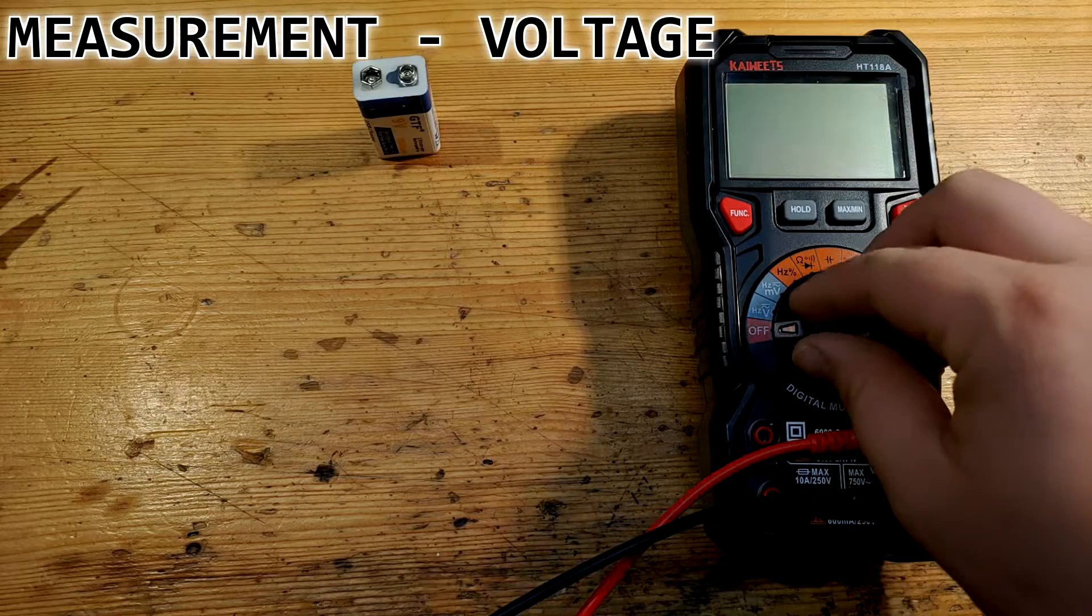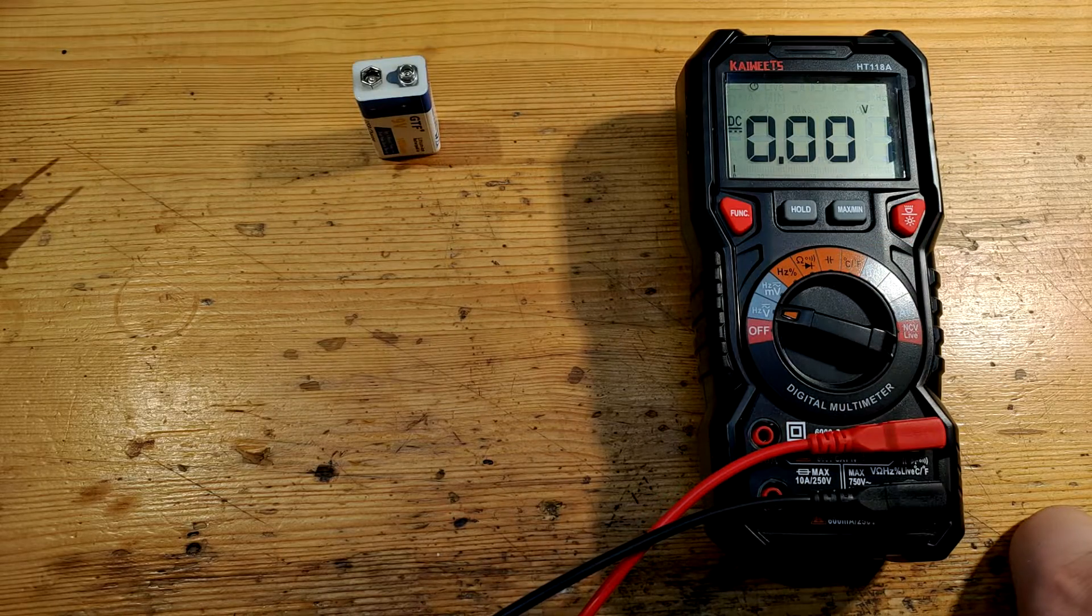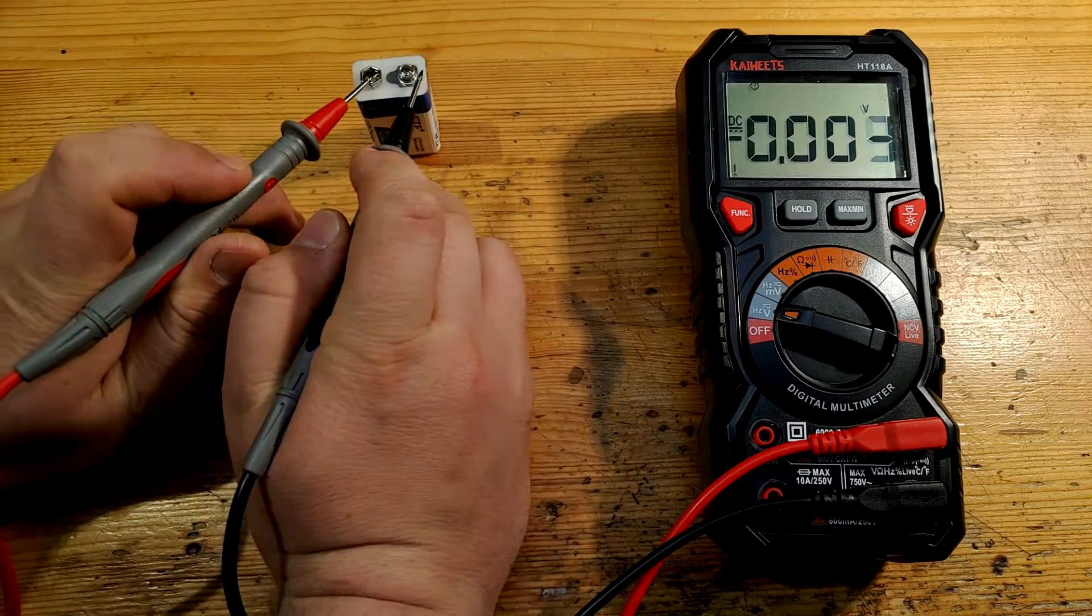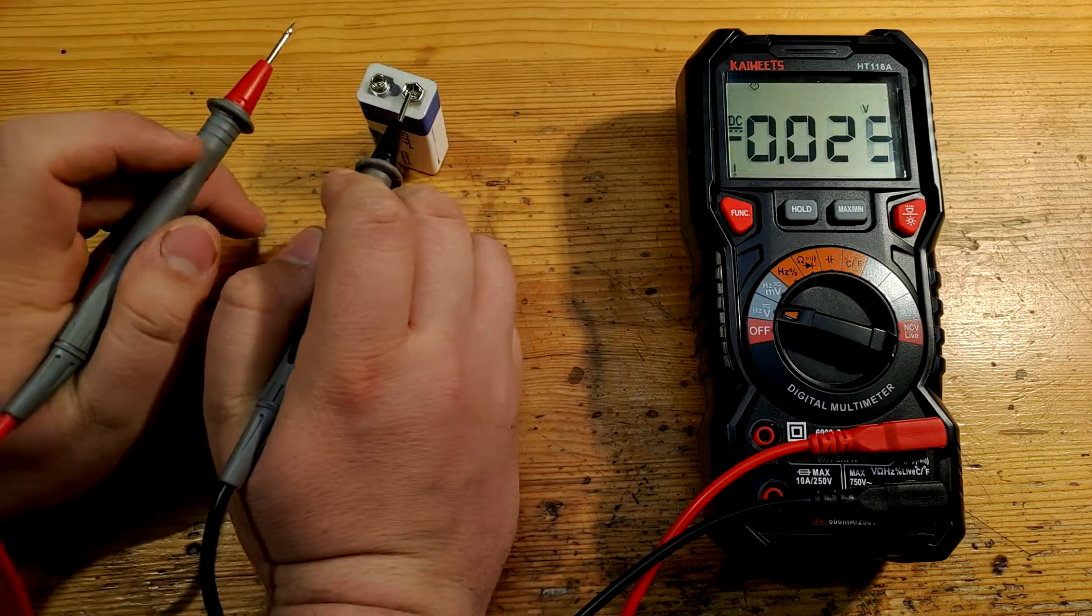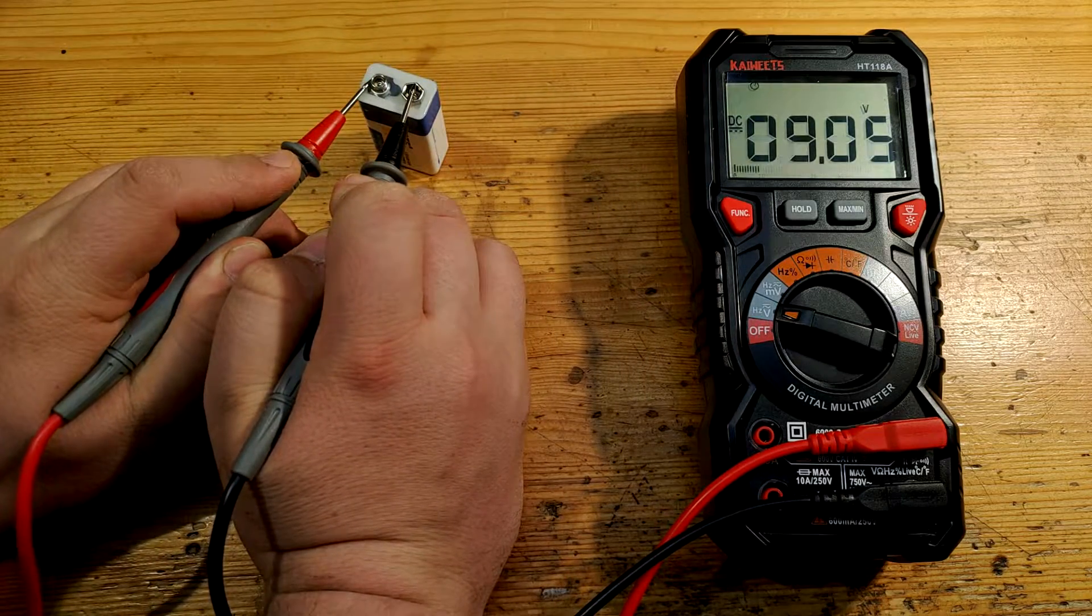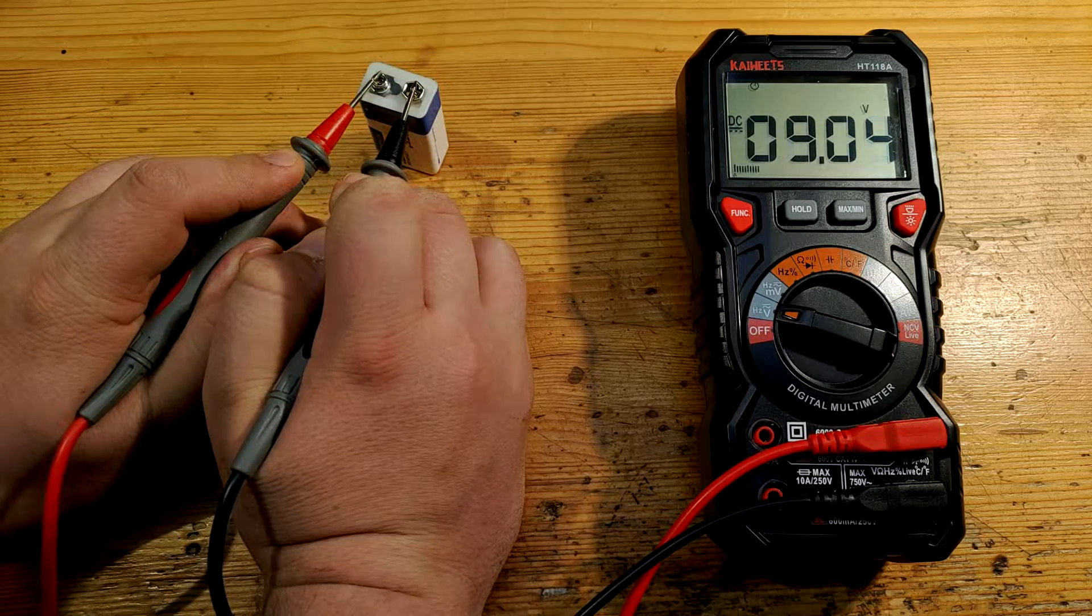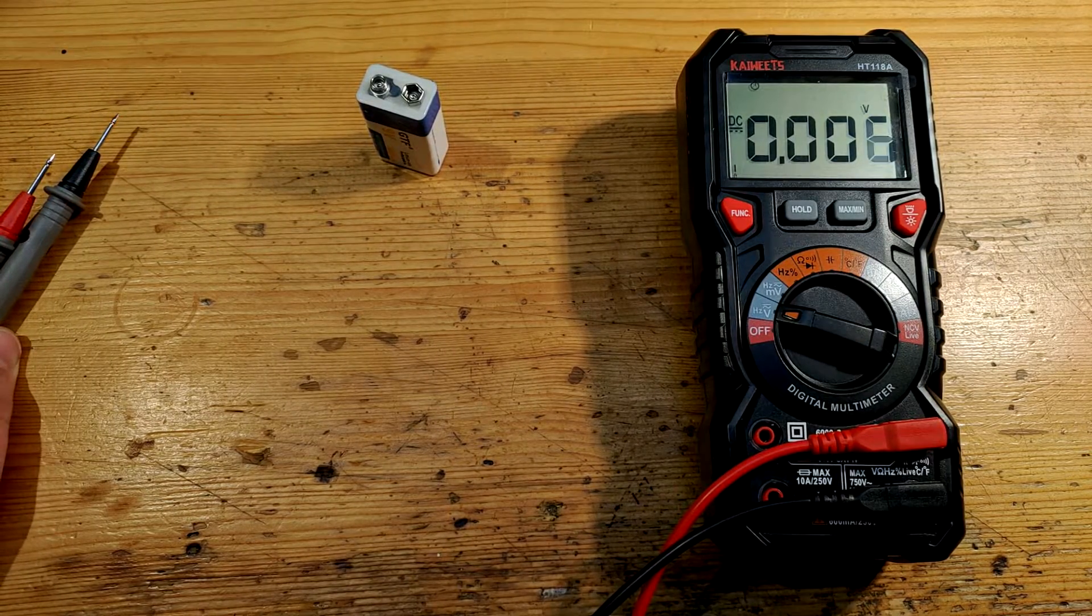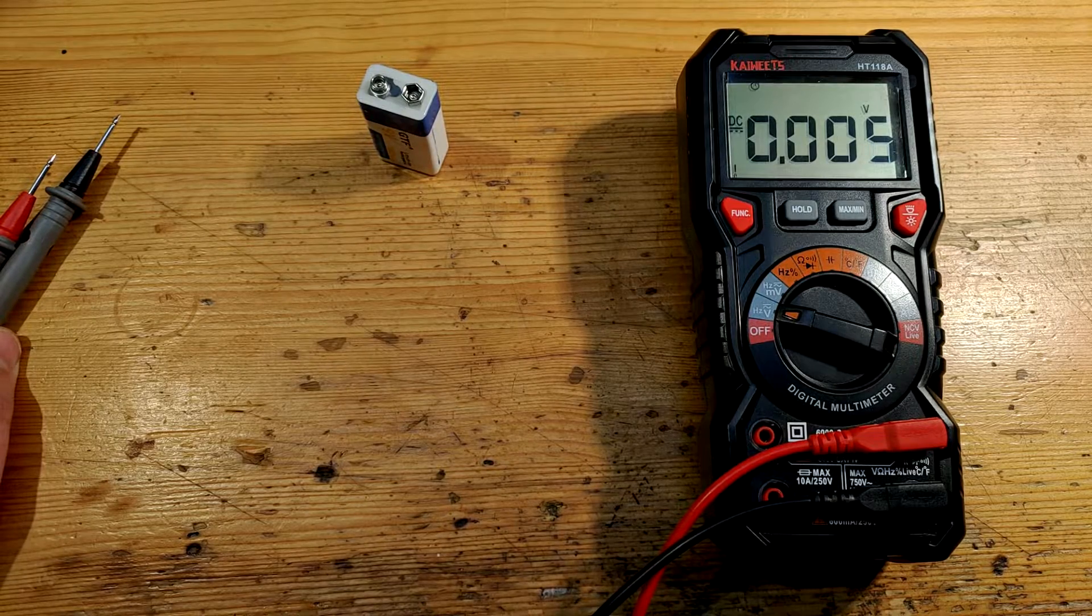Now, let's spin the Wheel of Fortune over one click and get to voltage measurement. The value stabilizes approximately after 1.3 seconds from voltage presence. There are, however, multimeters that need 2-3 seconds to integrate. But this multimeter needs 1.3 seconds, which is quite usual. There are also multimeters that spit out the value within half a second.